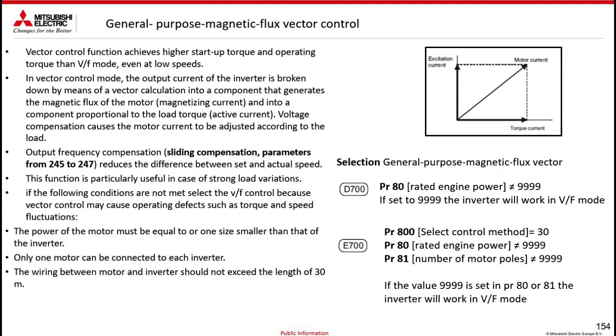If the torque boost is not enough, I would immediately recommend using a vector mode, such as general purpose, which is a simple vector control mode where the vector product between the excitation current and the torque current is given, which is then defined in a procedure called auto-tuning. To do auto-tuning, you have to pre-parameterize the inverter with the motor data, such as nominal current, motor technology, the kilowatts of the motor, the number of poles, the nominal frequency, and the nominal voltage.